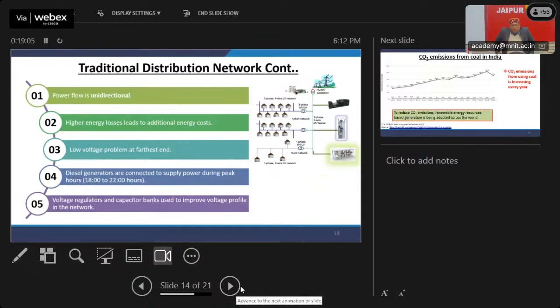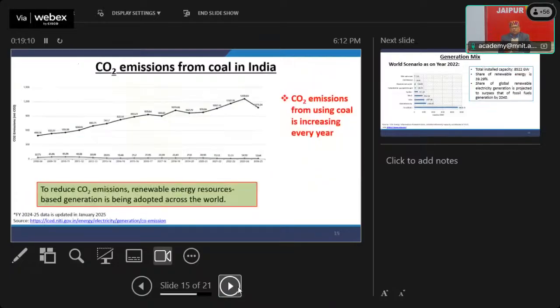Voltage regulators and capacitor banks are used to improve the voltage profile in the network so that all the time you get constant voltage. Now, this is an important analysis with a very interesting outcome. In the 2024-25 data, the carbon emission, CO2, has been increasing over the years. CO2 emission from using coal is increasing every year, and the characteristic keeps on increasing till the last point. But in the last couple of years, you could see the CO2 emission has drastically reduced. Why is it happening? Any clue? Renewable energy, because thermal power plant generation has been taken over. Basically, we stopped adding thermal power plants. So the carbon emission got reduced drastically in the last couple of years, and it is going to fall much more in the next 5 to 10 years.